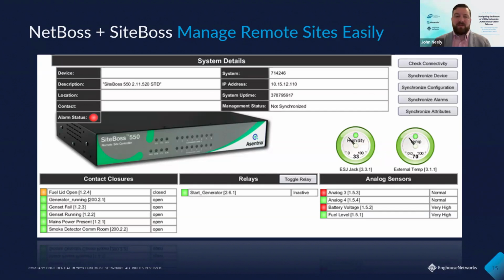This drill down also allows you to view non-alarm telemetry data, which is hugely important to determine why sites might not be operating as efficiently as possible, even if they're not operating so badly that you get a critical failure alarm. This often lets us see things like techs going into a site, changing the HVAC settings to be more comfortable, and not changing them back when they leave. Without a solution like this, that might run indefinitely, eating up unnecessary power. Using this unified solution, you can spot those problems and fix them right away, ensuring you're as resilient and efficient as possible.